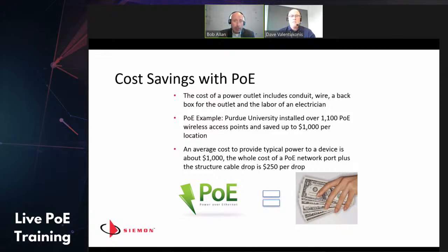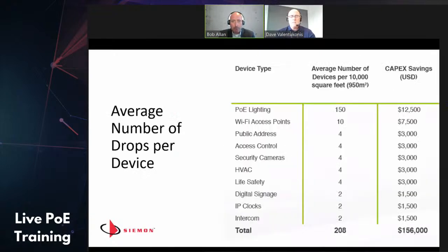We can bring PoE to that same location for about $250 — figuring about $100 for a powered port, and then about $150 for an open air category cable run. So if you were to leverage PoE for everything in a building, you'd add about 208 low voltage drops per 10,000 square feet. But keep in mind, every time we add a low voltage drop, we're eliminating an AC drop, and in most cases, an AC drop and a communication cable.